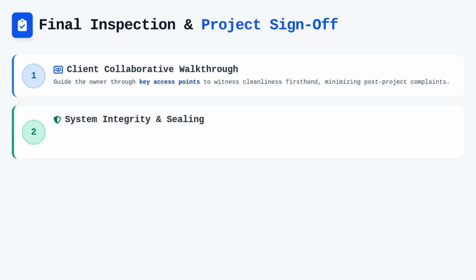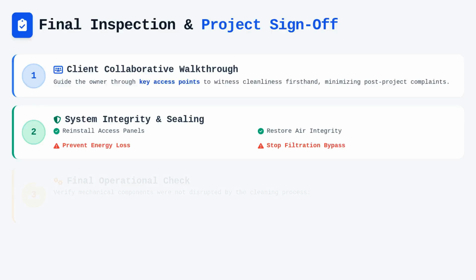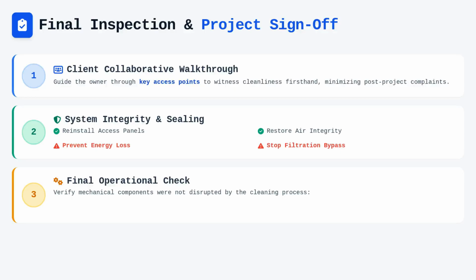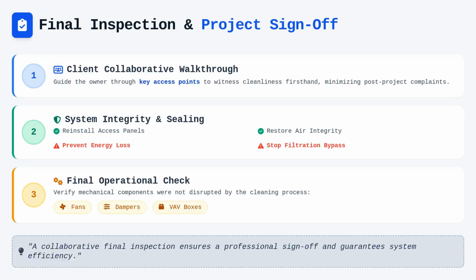During this walkthrough, you must also verify that all access panels have been properly reinstalled, properly sealed, and that the system's air integrity has been restored. Failure to ensure a tight seal on access doors can lead to significant energy loss and potential bypass of filtration, which defeats the purpose of the cleaning. Always perform a final operational check of the system's mechanical components, such as fans, dampers, and VAV boxes, to ensure that the physical act of cleaning did not disrupt any delicate movements or control signals.